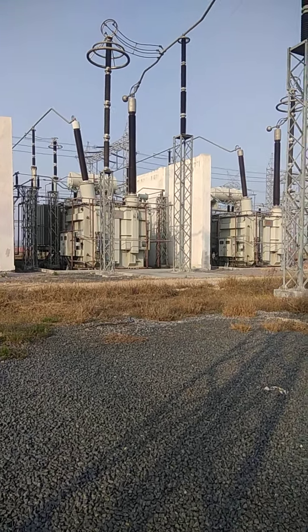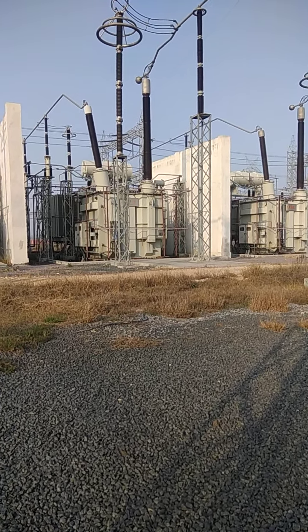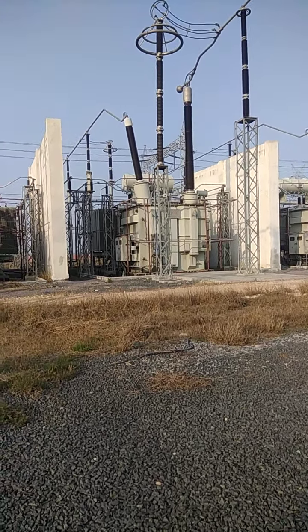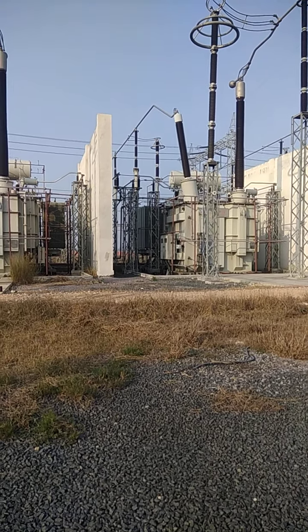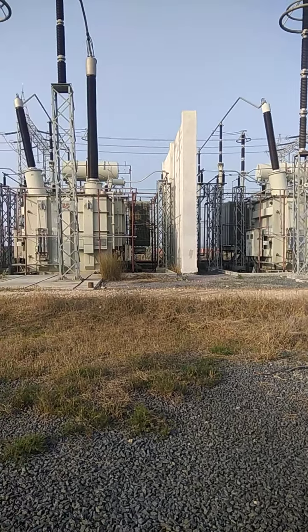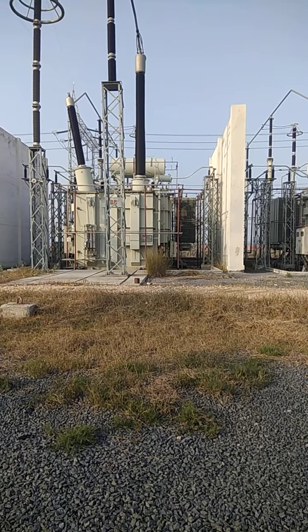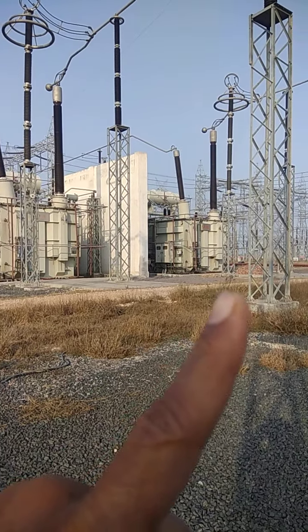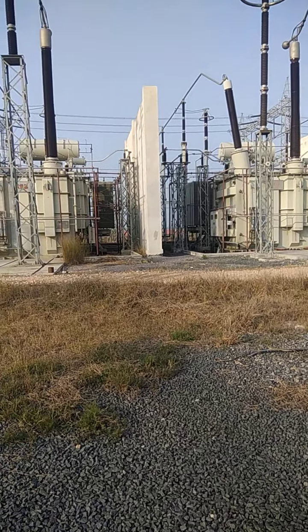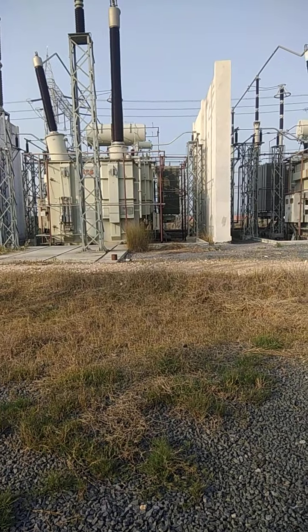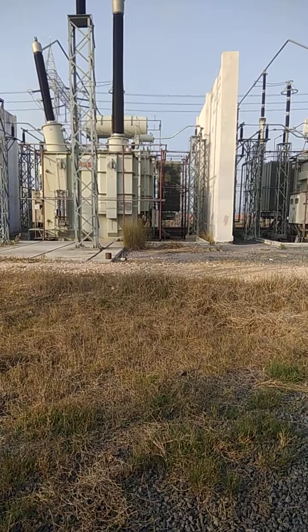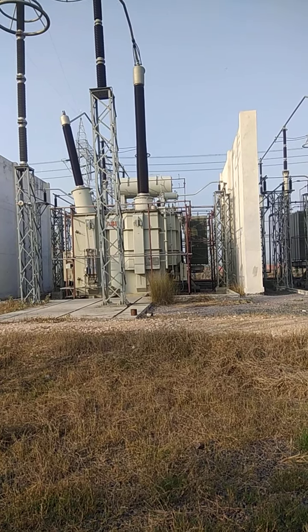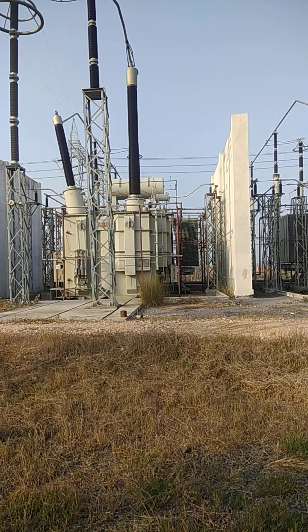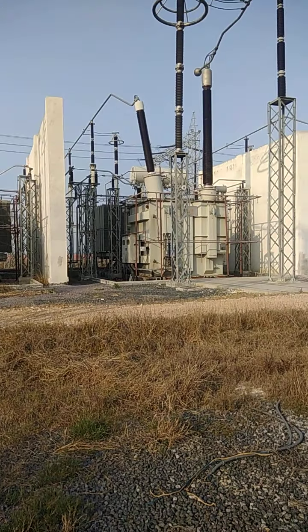But with single phase transformers, there are many challenges in our operation, also in the design. This is the R phase unit, this is the Y phase unit, and this one is the B phase unit. Here we will not discuss the design of transformers. We discuss only the arrangement of single phase units for a three phase combined unit.